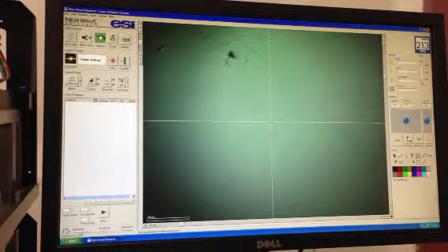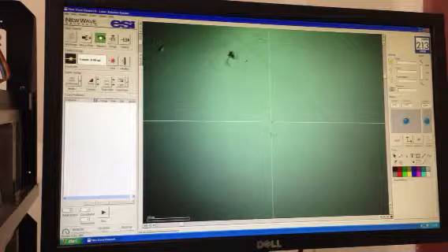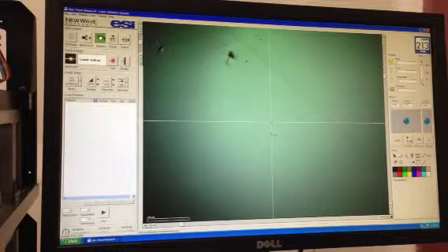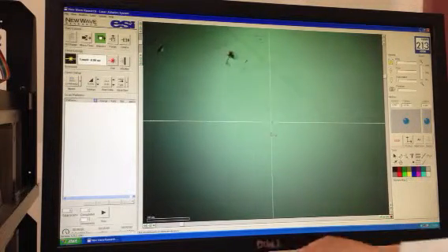Okay, this is a walkthrough of the Truline position compensation characterization test that was designed to be done in the field after upgrading a system to use the Truline stages. This assumes that the e-configure stuff has been set to turn on the Truline stages. All the gas handling stuff has been set. The system has been completely calibrated, including screen calibration, and the mechanical gap between the Truline sample chamber and the Truline top plate has been set and verified at 60 thousandths of an inch.